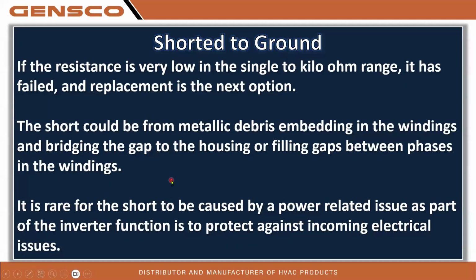So shorted to ground is going to be when the resistance is very low. Usually, when you measure it, it's a single number or it's a kilo ohm range. The compressor has failed. The short could be from metallic debris embedded in the windings and bridging the gap to the housing or filling gaps between phases in the windings. It is rare for a short to be caused by a power-related issue, as part of the inverter function is to protect against incoming issues.